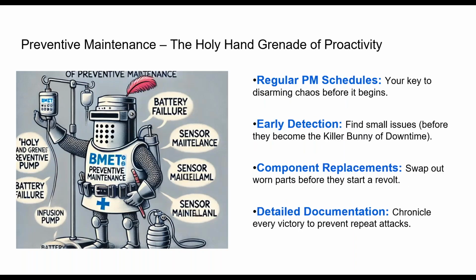So preventative maintenance - regular schedules. I can't think of a manufacturer out there that, if they prescribe a PM, does not have it on some sort of regular basis, usually annual in my experience. An AEM could throw that out the window. You could be looking at your pharmacy software to see how often a pump is used, or doing something else. But regularly schedule your PMs to disarm things before they become a problem.